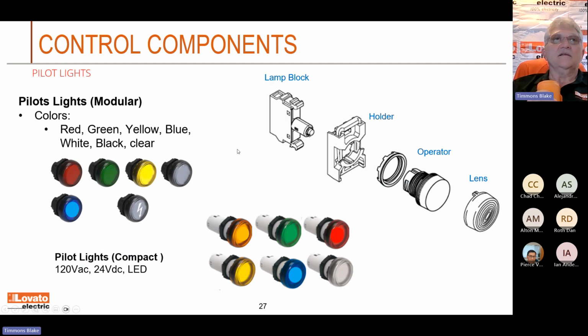Pilot lights. Okay, here are the different ones. With the modular one, as I'm showing here, you have your lens, your operator, that lock nut, the holder, and then a lamp module that fits up inside there. Or you can have these monoblock ones down here that are all built into one. You don't have to put all that together. Typically, OEMs like these monoblock series where everything's built into one. Otherwise, most people will get the modular ones, and then they can mix and match whatever contacts they want to put on the back of it, whatever color they want to use. They can minimize the inventory.